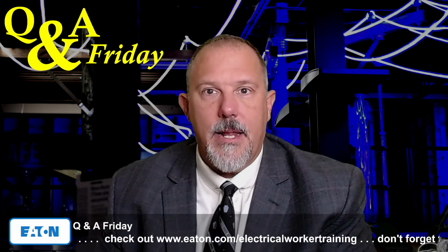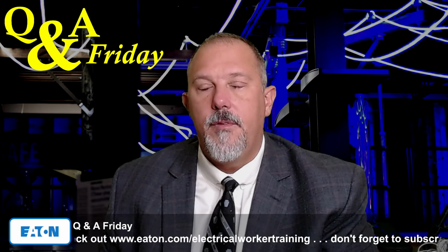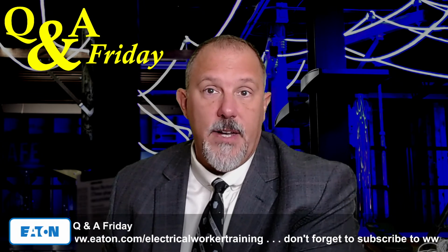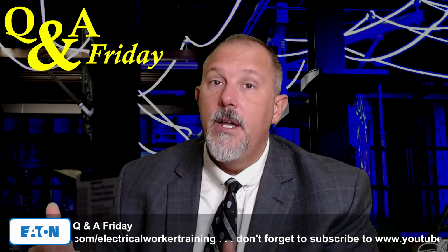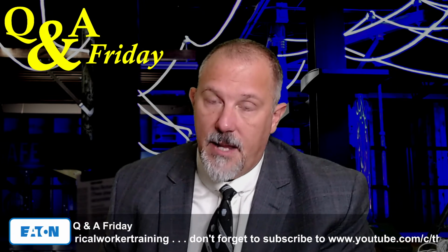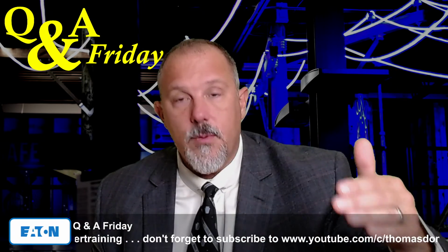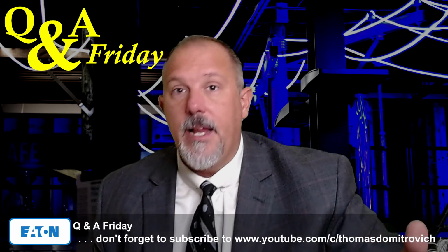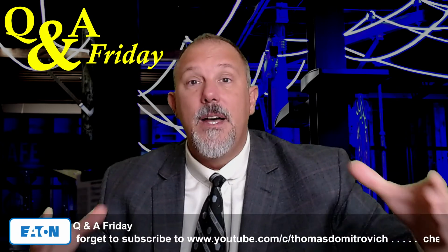So I can have a very high bolted fault current value, and I'm worried about the interrupting rating of the downstream device, because in a series rated system, the downstream device has a 10,000 amp interrupting rating and the upstream device has a 65,000 amp interrupting rating. Together, they can interrupt up to 65,000 amps.